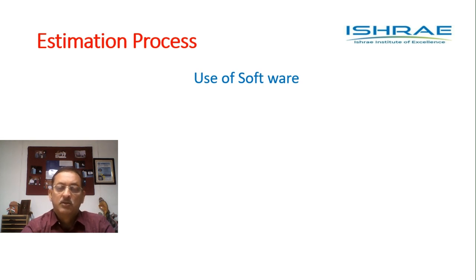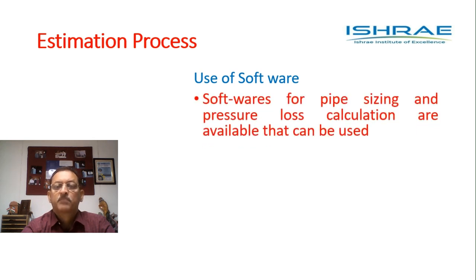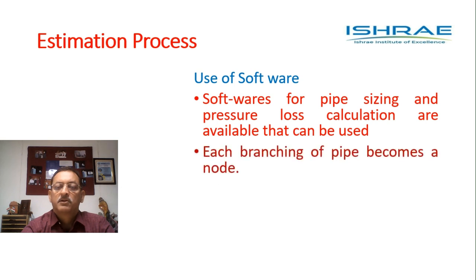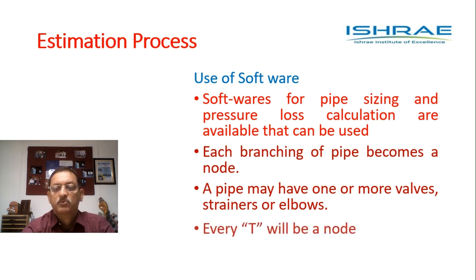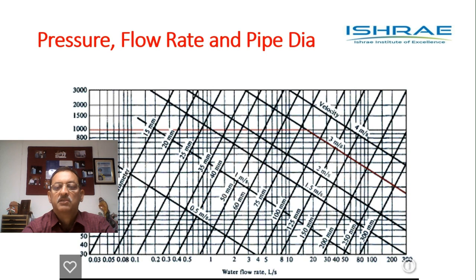A pipe may have one or more valves, strainers, or elbows. There are softwares like PipeNet which help in sizing the pipes, estimating pressure loss, and selecting the most suitable pump from a range of pumps. Each branching of the pipe becomes a node, but valves, strainers, or elbows within a pipe section do not necessarily become nodes. Every T-piece becomes a node because every T has a branching taking place.